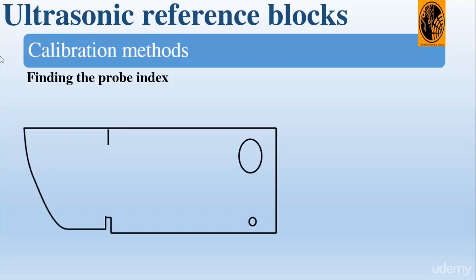First, let's start by finding the probe index. The point at which the center of the beam leaves the probe and enters the test material is called the probe index, or the emission point. It should be marked on each side of the probe and checked regularly. To find the probe index, as you can see on this animation, we place the probe on the V1 block.